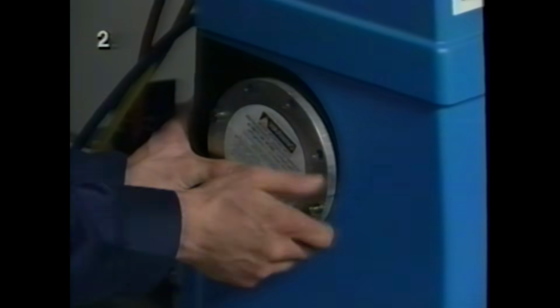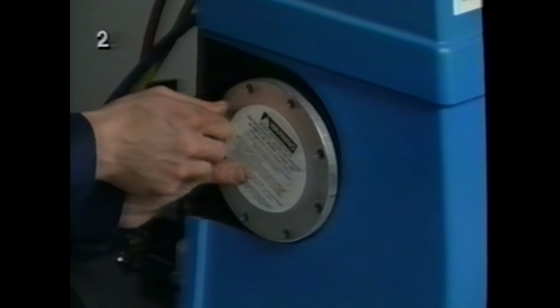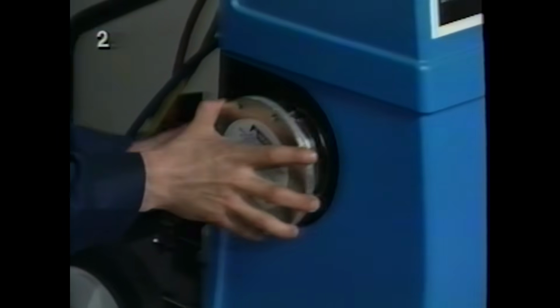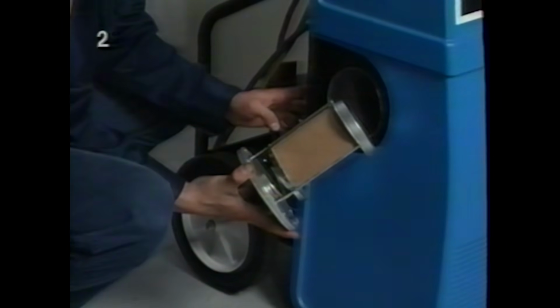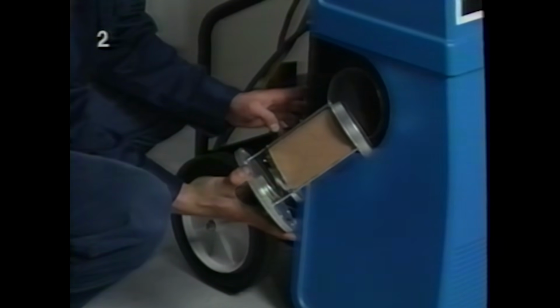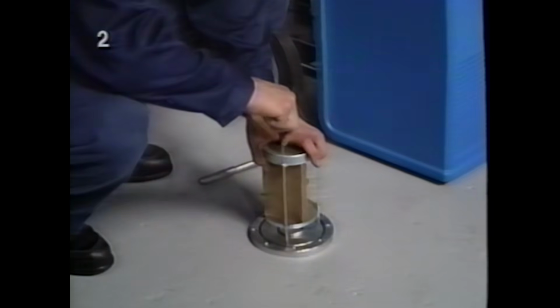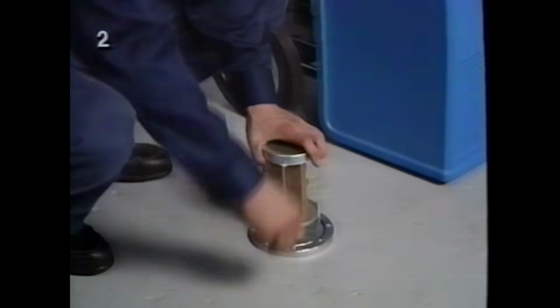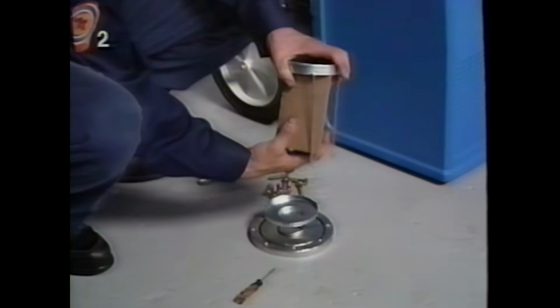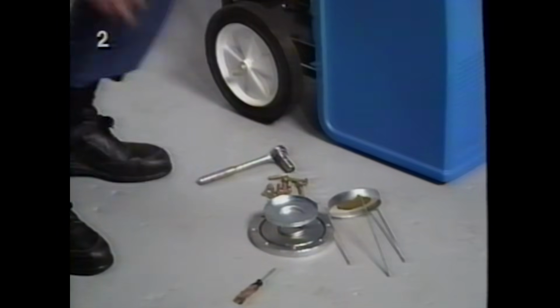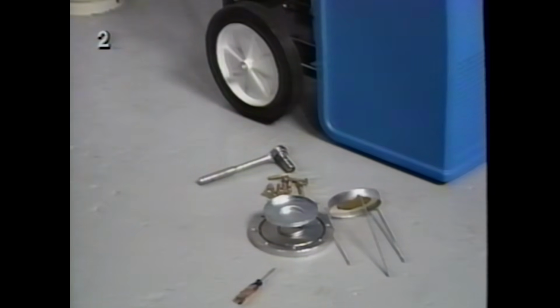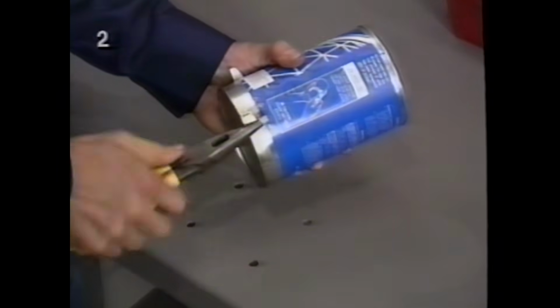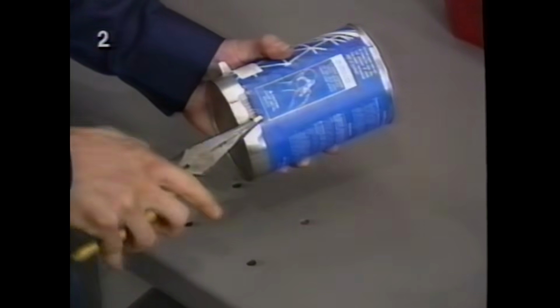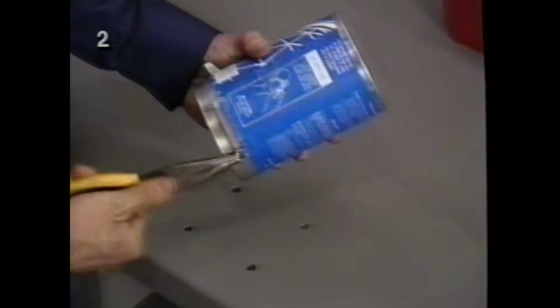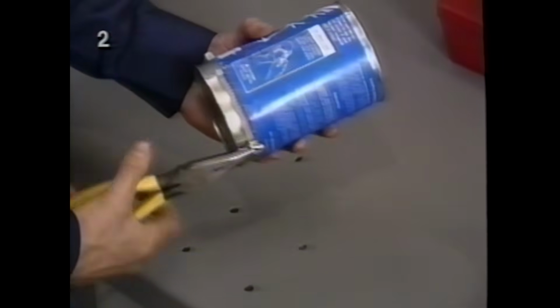When you use the ACR3 station for the first time, you have to install the filter dryer assembly. Take out the screws that hold the filter cap on its shell. There's a bracket inside that goes to the filter dryer core. Clean everything off with a lint-free cloth and throw away the little piece of cardboard. The filter dryer core is inside a sealed can. Take it out when you're ready to install it and use a new filter cap gasket if the old one is damaged.